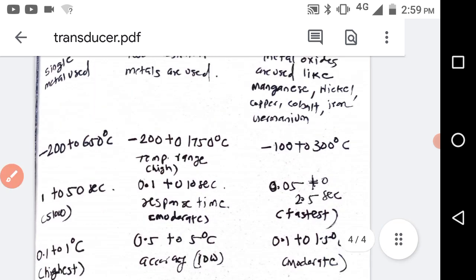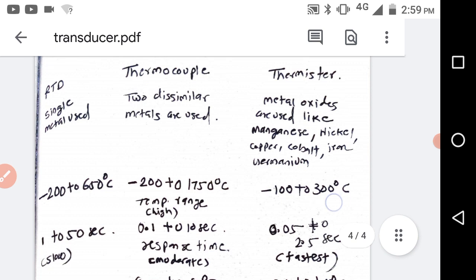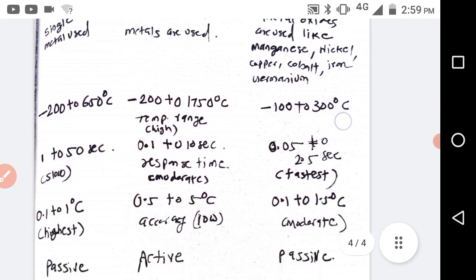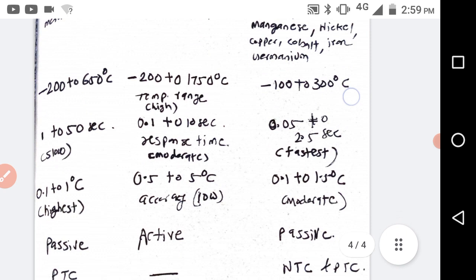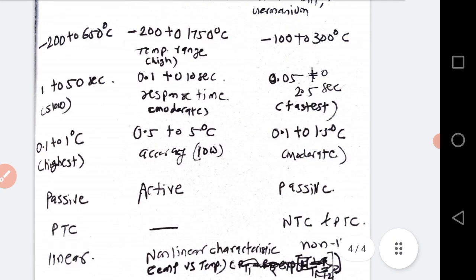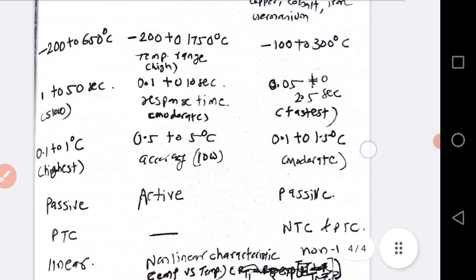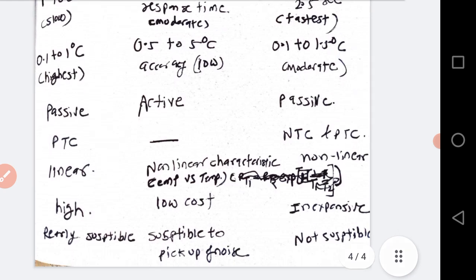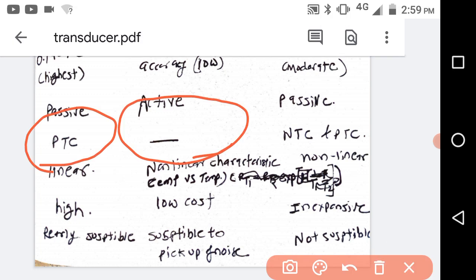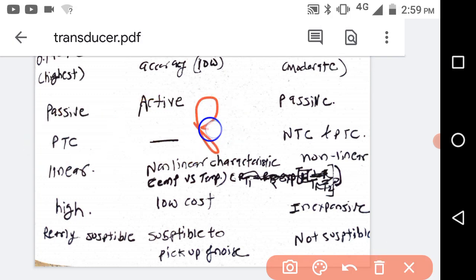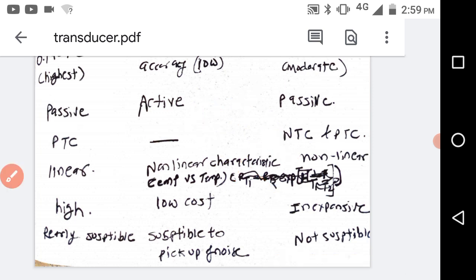So, till now, we have seen that the maximum temperature range is covered by the thermocouple, then response time is highest of the thermistor and accuracy is highest of the RTD. So RTD highest accuracy, response time highest of thermistor, temperature range highest of thermocouple. So thermocouple is active and RTD and thermistor are passive. So RTD has the positive temperature coefficient, that means its resistance increases with increasing temperature, and thermistor has negative temperature coefficient as well as positive temperature coefficient, that means its resistance can increase or decrease depending on whether it is NTC or PTC.